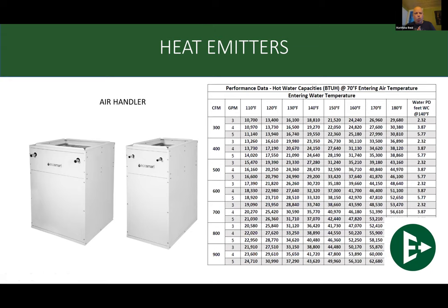So we have the heat loss for the house was 16,500. So if I'm going to be doing it by an air handler, I can size that air handler quite simply. We look through the charts for what we have existing. Now, this is from a friend of mine, the friends over at EcoSmart, that have graciously provided to me the BTU capabilities of their air handlers. So I know that if I need 16,500, I can size a pump at 4 GPM, run this thing through at 130 degrees Fahrenheit, well within the condensing temperatures, which we'll get to, and at 300 CFM, I'll be able to get the heat loss into my house with this particular model of air handler that they're talking about.